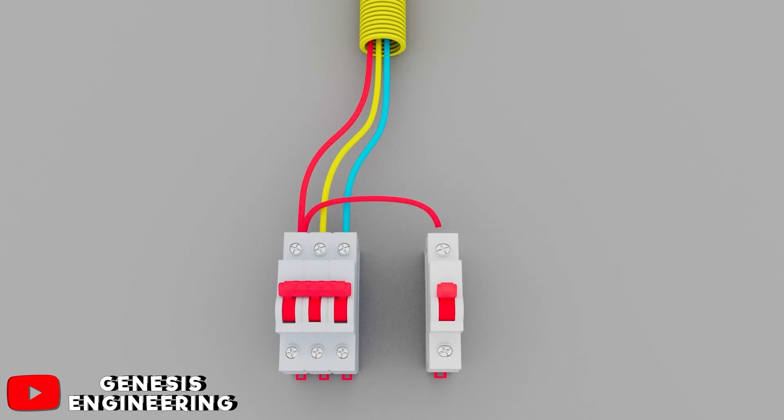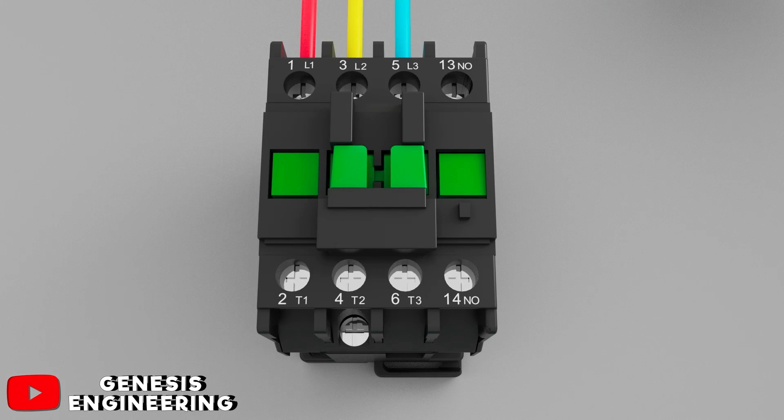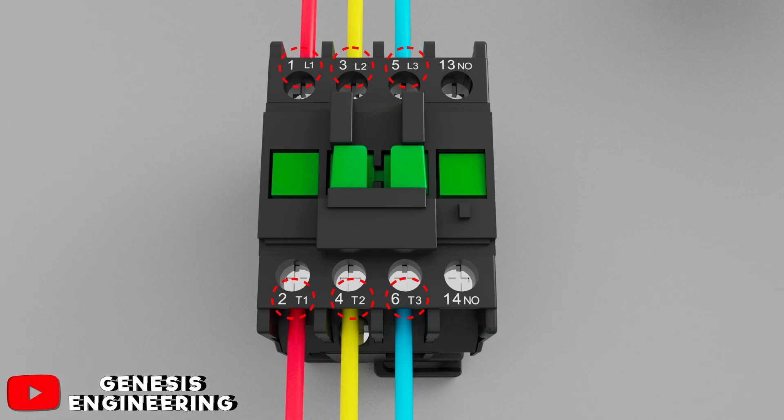Making a contactor connection, we start with the power circuit, connecting the three-phase conductors to the three-phase general circuit breaker and then we leave with the three conductors and connect to terminals 1, 3 and 5 of the contactor, and contacts 2, 4 and 6 we connect on the motor.